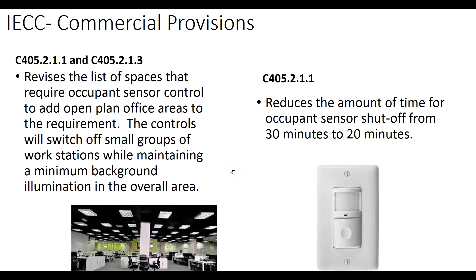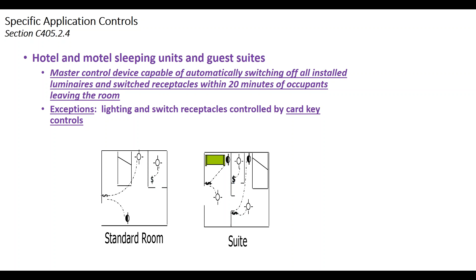Hotel, motel, sleeping units always used to say that you have a switch when you walk in the door that turns on some fixtures. This was so that when you're walking out of the space, there's a switch by the door. You might shut it off, but if you got to go back and shut off a lamp and you got all your luggage in your hand, you're probably not going to do it. Well, now that's not in there. So now it says you either have a master device capable of automatically switching off all the installed lights within 20 minutes of the occupant leaving the room. So an occupancy sensor or some type of sensor that says you'll leave, or a card key device where the lights shut off when you take your room key out of it. Right? So when I leave the room, I'm going to need my key to get back in, so I'll take that key out.